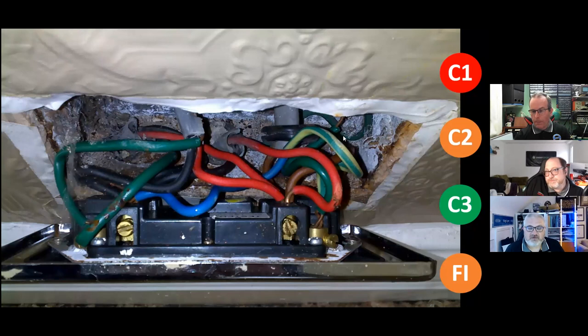Do you know what? Without knowing any more, I think it's a C3 and an FI. Mm. I do. I think it's assuming that everything else is technically okay. We have RCDs. We have an accessory that's not damaged. Is there any risk or is there any evidence of thermal impact, thermal effects in there? Doesn't look like it.